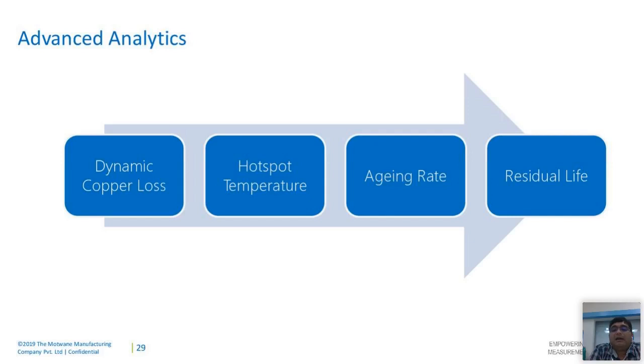And when these values cross the limits where the depolymerization of the insulation is accelerated, those scenarios are captured, and then we calculate the aging rate. That is the rate at which the transformer insulation is aging, or the depolymerization of the insulation is happening. Of course, there are other methods, but this is one which works on real-time and instant data. Other techniques, which are part of offline testing, can also be deployed to further validate it. But as I said, this is the input you get in real time.